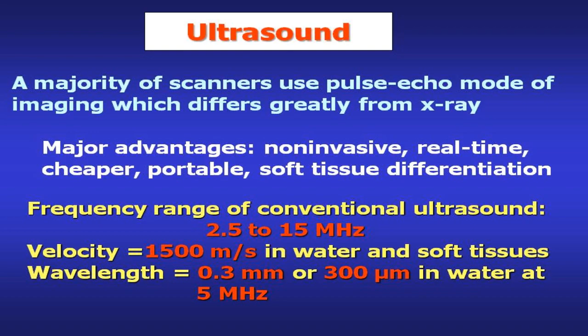So at 5 megahertz, the wavelength is 300 microns. In other words, at 5 megahertz for clinical scanners, the spatial resolution is about 300 micron. So you can identify objects as small as 300 micron.